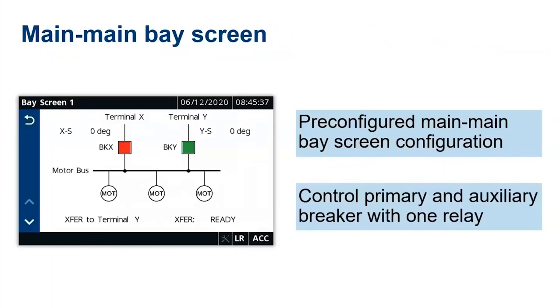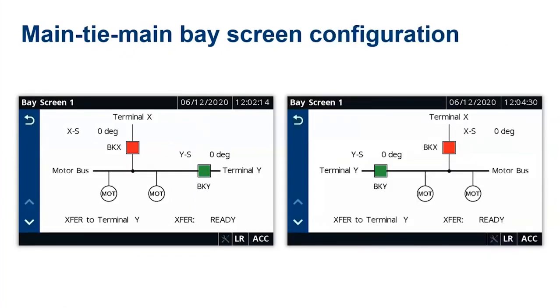Okay, for each of these applications, we have default bay screens that will show in the relay, and you can go directly and control open this breaker, and it will start. You can tap on the screen, open the breaker, and it will automatically do the transfer to the other feeder. So we have this one for the main. We have these two, one for each of the two relays in a main application. Yeah, and you can download this directly from the website.